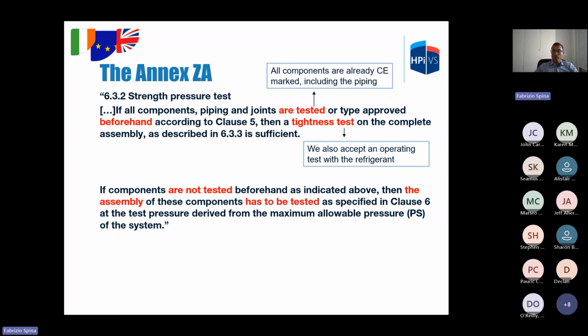We have basically two cases. The components already tested, so that means already CE marked, and components that are not tested, for example the piping, when the manufacturer also manufactures the piping within the assembly. For the components already tested, we don't need to witness the pressure test, so we accept an operating test or a leak test. For the manufacturer items, a strength test is required.